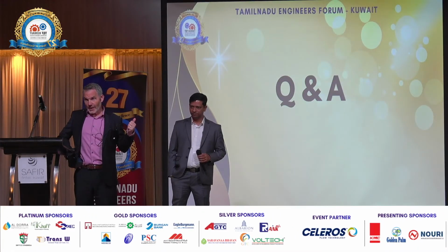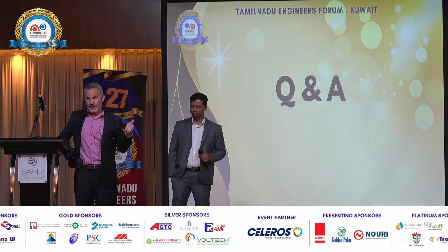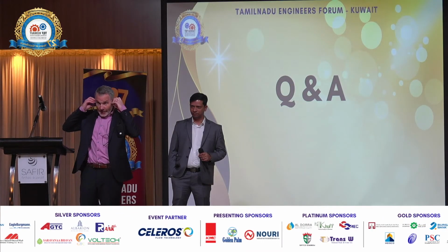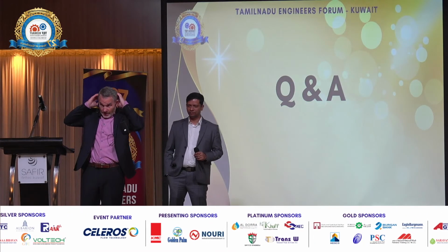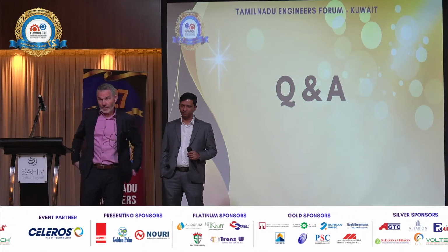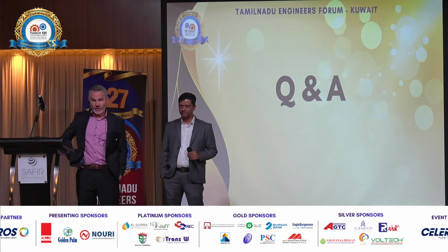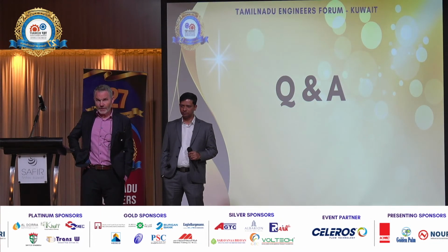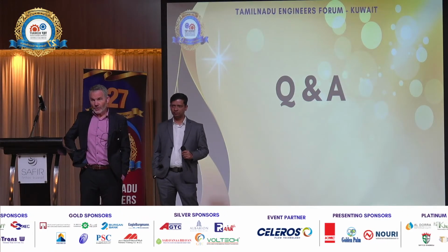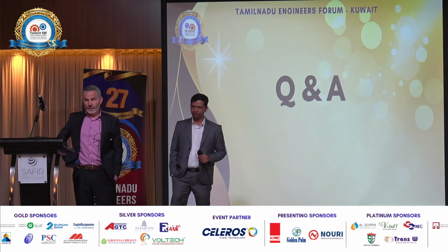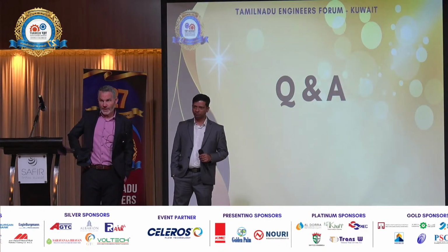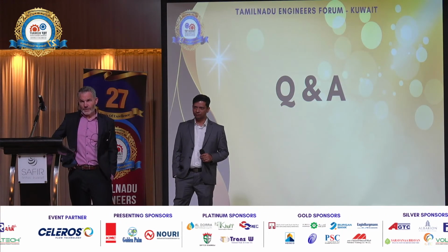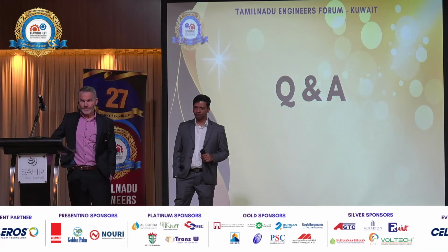Now, we've had pumps at ADNOC, I went to see them myself, one of the water injection pumps, believe it or not, ran for 20 years without any maintenance. The other pump that they pulled ran for 9 years, and the only reason they pulled it was they just wanted to see the condition. So if you're looking after the pumps, they'll look after you. You can have pumps running well beyond 10 years without any intervention. Again, a lot of it depends on the application as well.